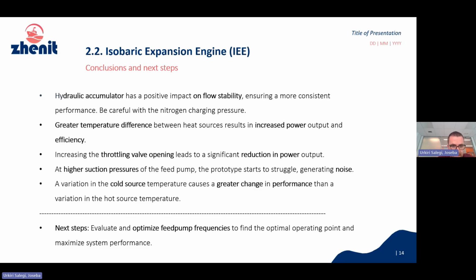Apart from that, suction pressure in the feed pump, as I mentioned, could be critical because, the higher the suction pressure we had, the more the noises and all the preoccupation started. So finally, we decided to decrease these pressures using lower supply temperatures in the condenser.